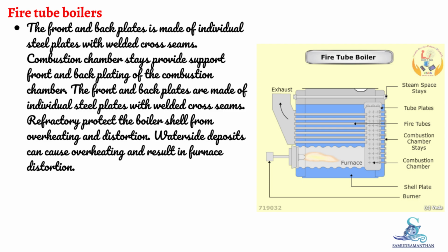Combustion chamber stays provide support to the front and back plating of the combustion chamber. The front and back plates are made of individual steel plates with welded cross seams. Refractory protects the boiler shell from overheating and distortion. Waterside deposits can cause overheating and result in furnace distortion.